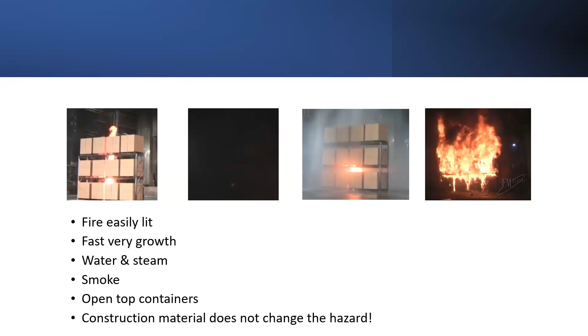Continuing on with evidence, I found that there have been quite a lot of tests subsequent to this, but when I was looking back in 2015 time, I was finding this. So there were some tests done on the AutoStore automated storage and retrieval system. They tested them with ceiling-only sprinklers because that's all you can do for these systems. You can't put an in-rack system in, there's no space. And they activated their systems, and then they went in afterwards with, in red here, it says, firefighting after completion of the test was undertaken by activation of a separate water deluge system over the array combined with crews with handheld water nozzles working from scissor lifts. Crews use traditional fog jets and with foam injection to create non-aspirated low-X foam, which they were finding was more effective. But if you go back to these big systems, there is no access for your fire service.